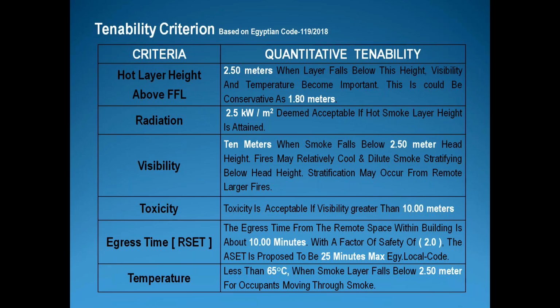So the fire load is a little bit small, but it increases rapidly until it reaches steady state, or a fully developed fire, okay? So the smoke moves under the ceiling. The radiation of the smoke layer shall not exceed a certain amount. Why? To be sure that it will not reach their breathing level, and to avoid the radiation effect, which is declared in the second point, from them to their heads.